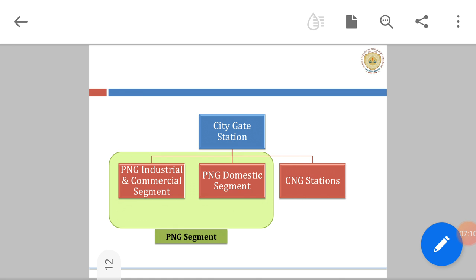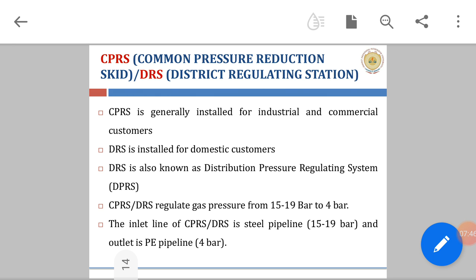Now we will talk about the common pressure reduction skid, CPRS, and the DRS, which is the district regulating station. CPRS is generally installed for industrial and commercial customers. DRS is installed for domestic customers. DRS is also known as distribution pressure regulating system, or DPRS. CPRS and DRS regulate gas pressure from 15 to 19 bar to 4 bar. The inlet line of CPRS and DRS is a steel pipeline with a pressure of 15 to 19 bar, and the outlet is a PE pipeline with 4 bar pressure.